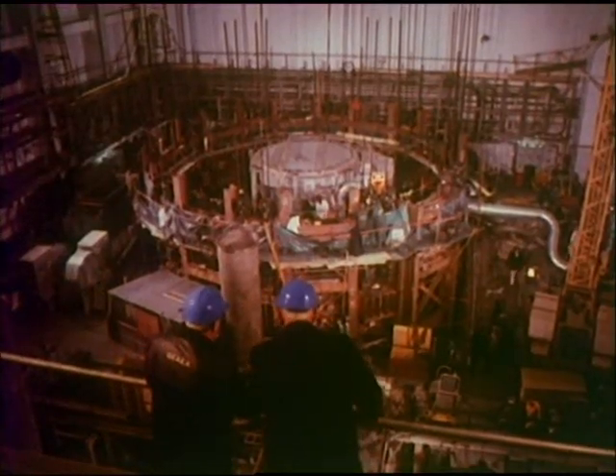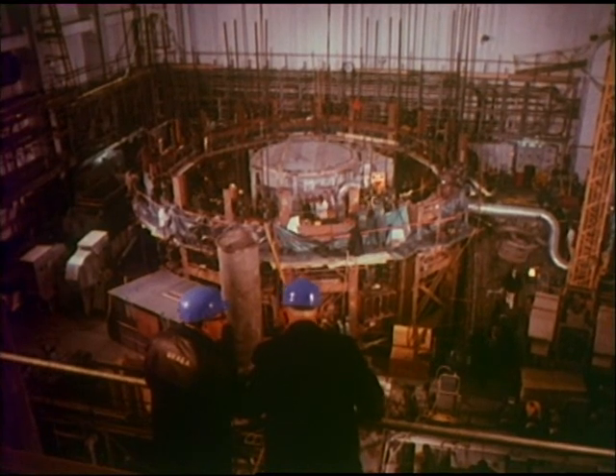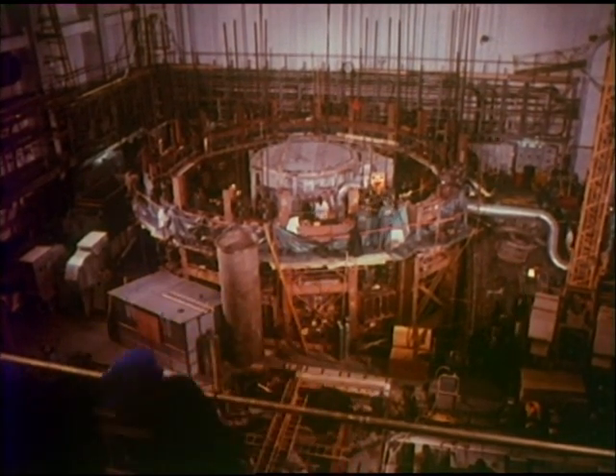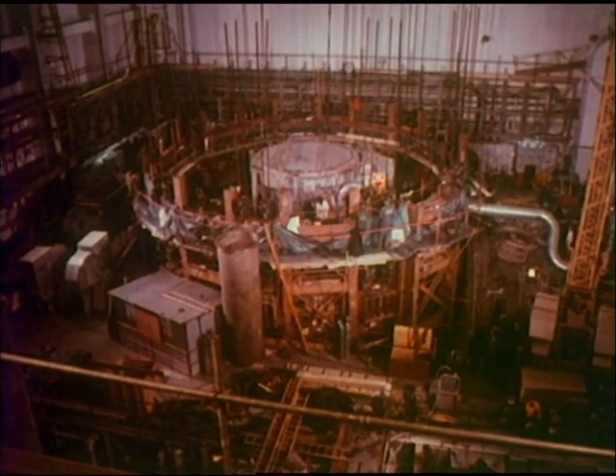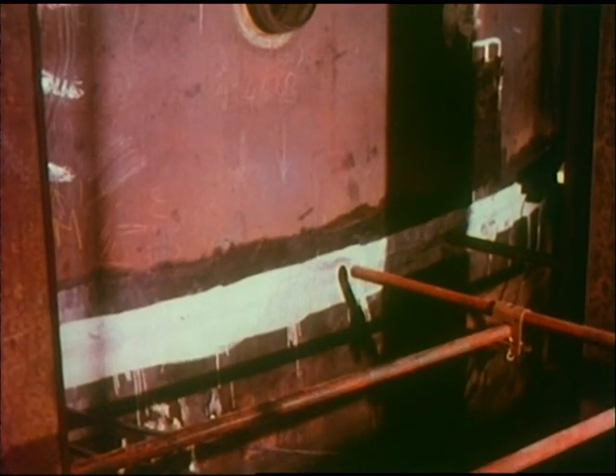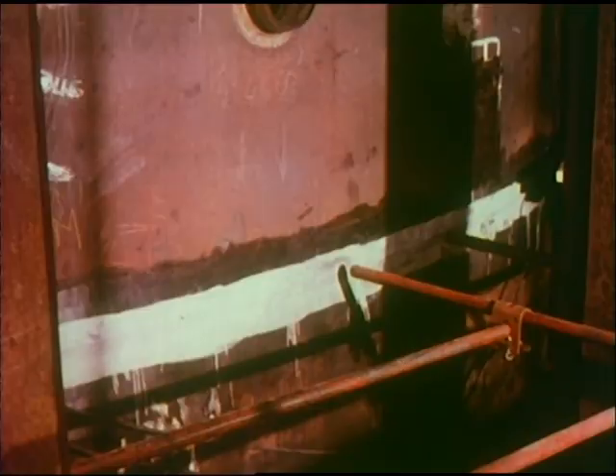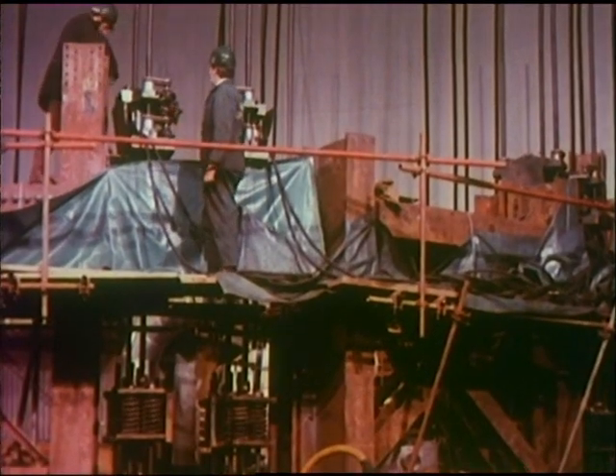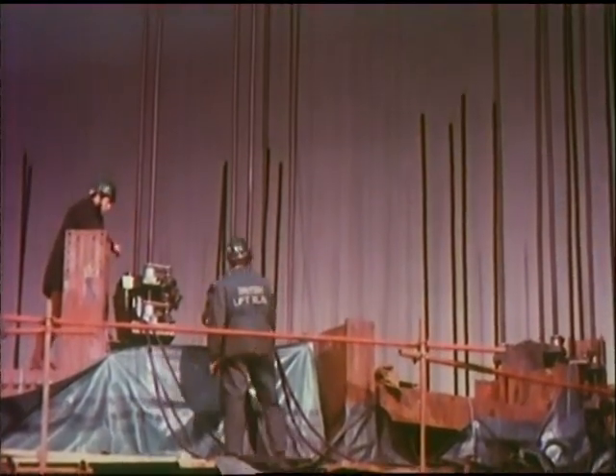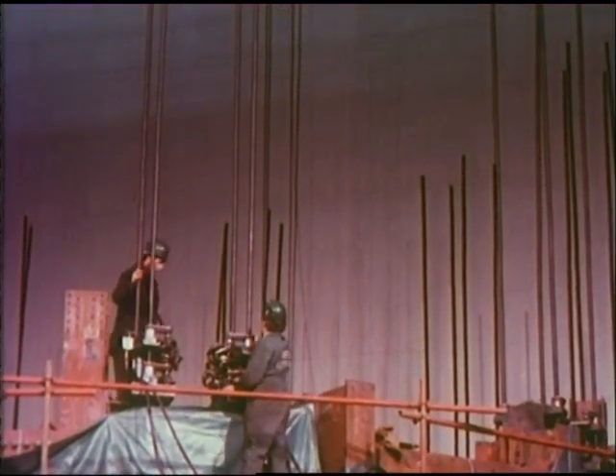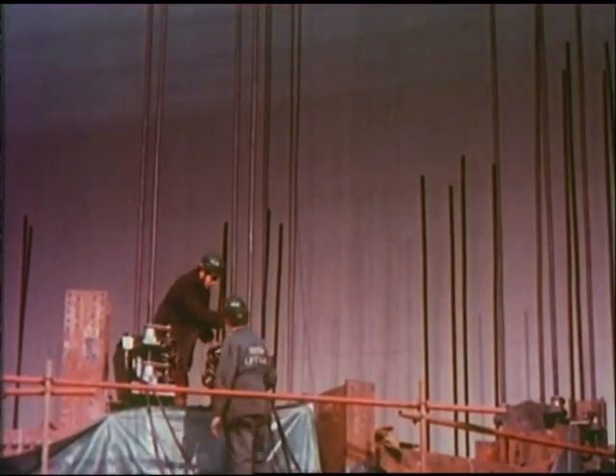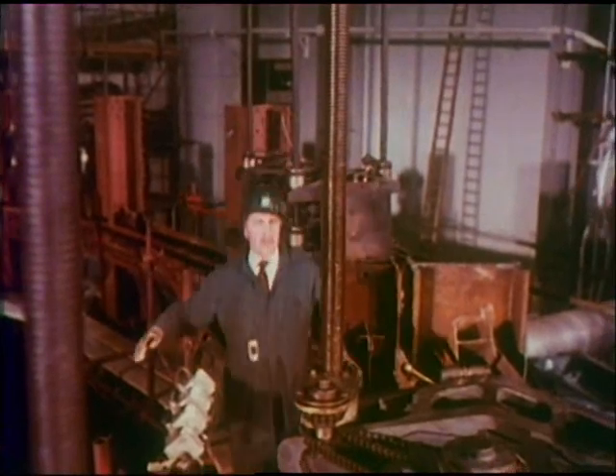During 1971, the reactor roof had been assembled on the framework above the vault, and the leak jacket, together with other reactor vessels, had been raised and welded to it. In January 1972, the completed assembly, now weighing some 1,500 tons, was lowered in one piece with the aid of a lift slab jacking system.